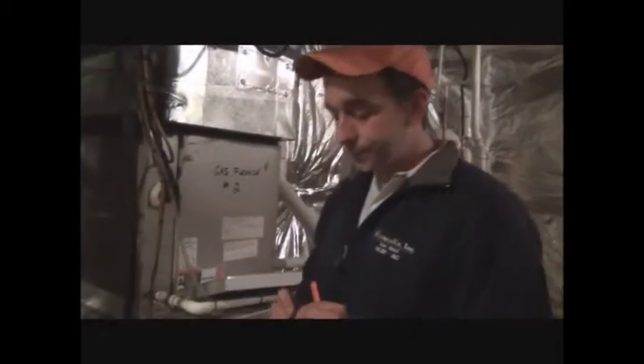So you want 80 square inches of duct per ton of air. You've got 264 square inches on this duct right here, so that's your supply. Your supply duct is undersized for the amount of air you're trying to force through there.